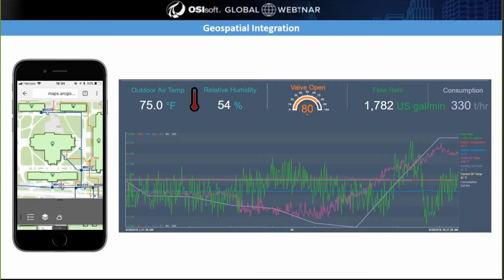If you've got 300 buildings all with chilled water supply from a central plant, and you want to see these 5 parameters for all buildings, you can templatize with the PI system, build that screen once, and then push it across all of those additional screens with a little bit of work. This eliminates one of the expensive services typically provided by automation system vendors, which is the creation of graphics. So using templates is a very efficient and cost-effective way to create visualizations.